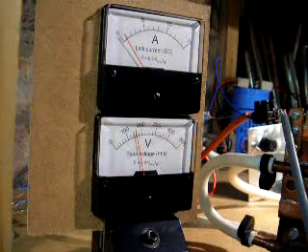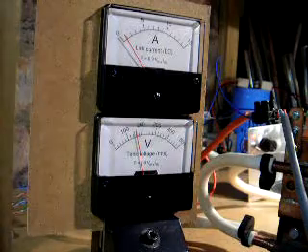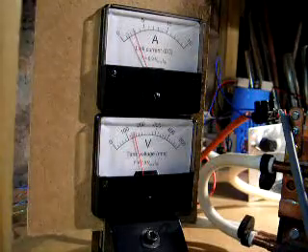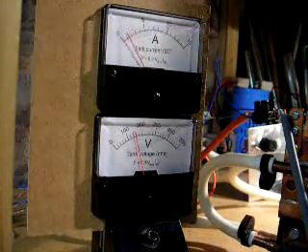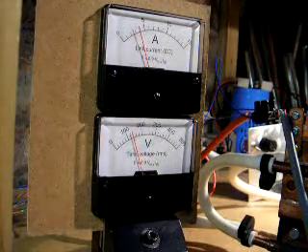If I now insert a load — for example a crucible into the tank — you'll see the link current increase as it begins to draw power, and the tank voltage decrease slightly.